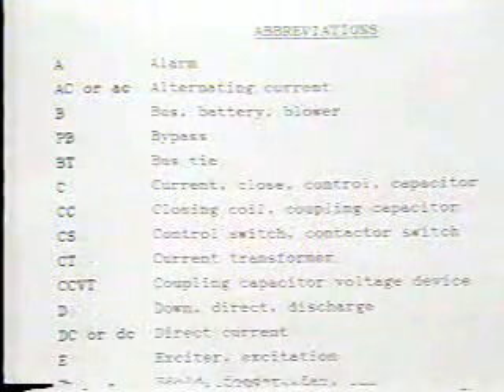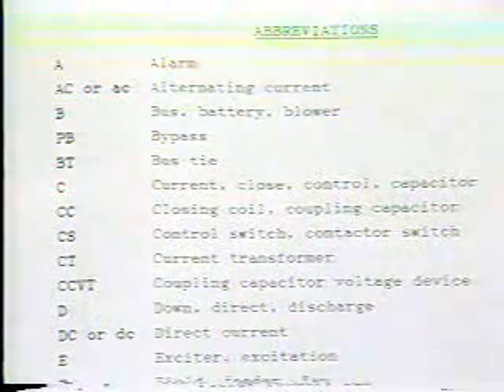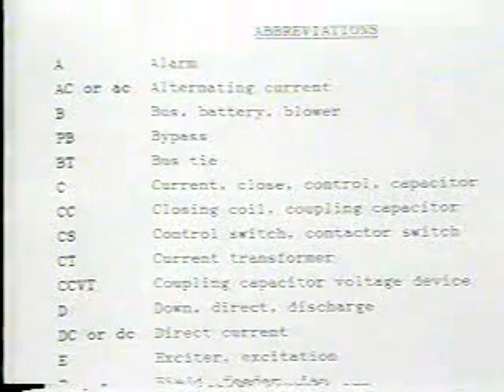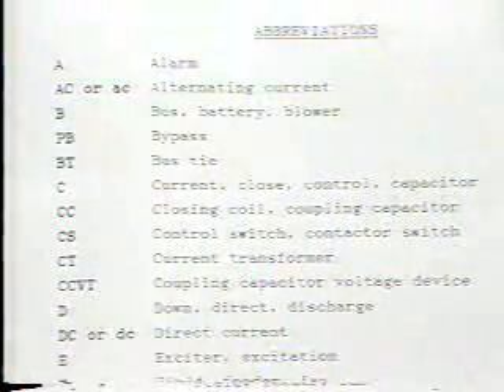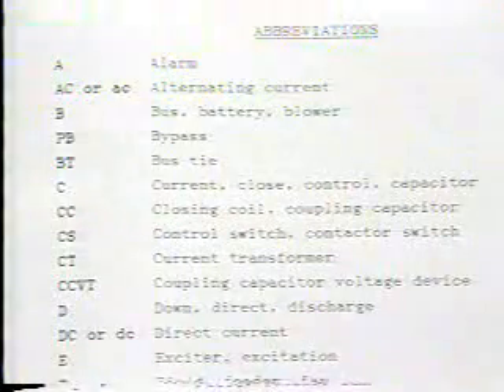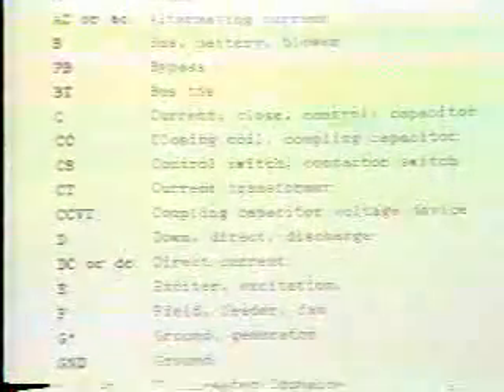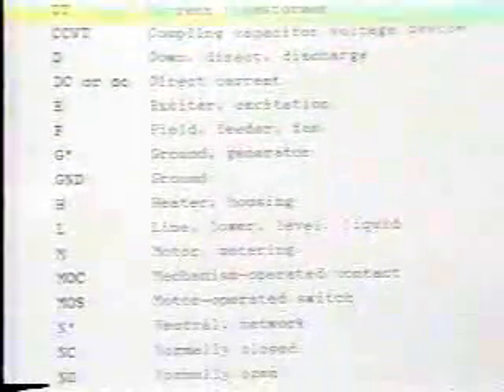In addition to device numbers, a list of abbreviated letters are also provided. And here we can see just at random that A is an abbreviation for alarm. CS represents a control switch or contactor switch. G indicates ground or a generator. N stands for neutral. TC for trip coil, and so on. Now, there is no need for you to remember all of these abbreviations or device numbers. A list is included in your workbook.